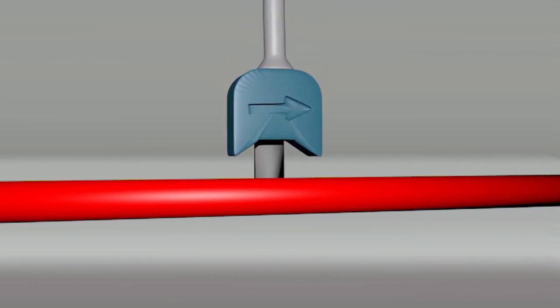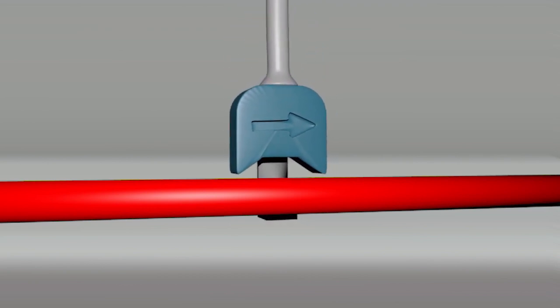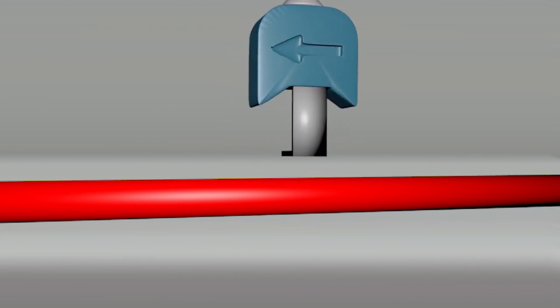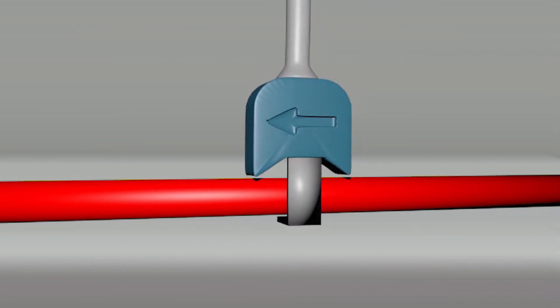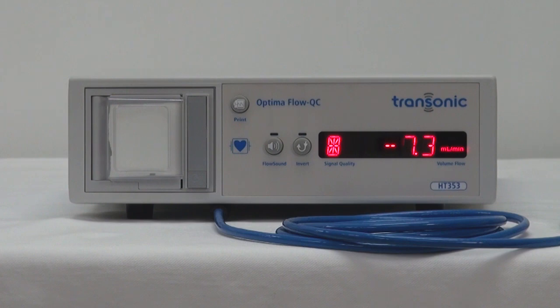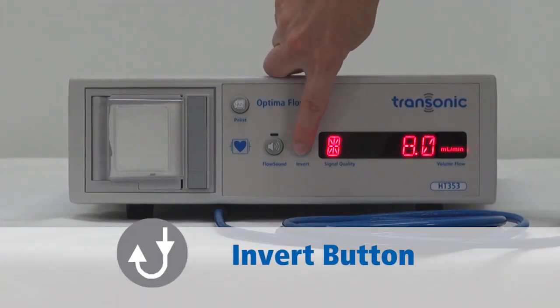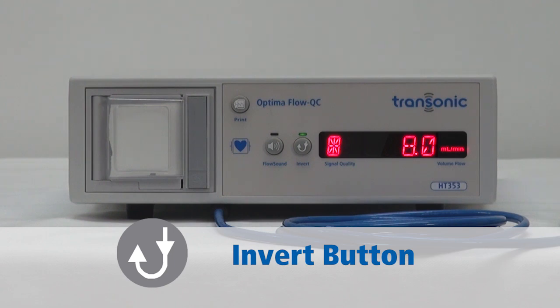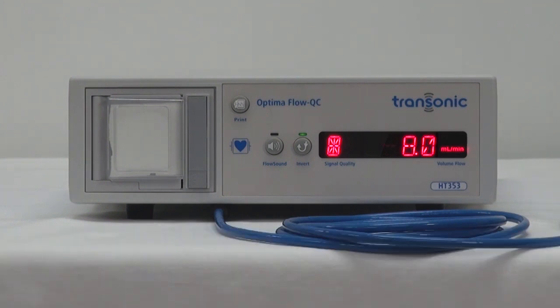The flow probe may be oriented in either direction relative to flow. Positive flow is in the direction of the arrow on the head of the flow probe. If flow is in the opposite direction, the invert button can be pressed to invert the flow waveform and mean flow value without having to reposition the flow probe.